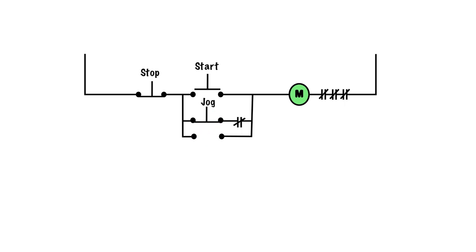And I have actually physically seen it happen many, many, many times in our labs where I teach, just to prove that this circuit. I would say about 50% of the students that wire it up, it works fine when they hit the jog, it just jogs a button. But the other 50%, if they do it quick enough or they kind of hit that button really quickly, it bounces back and the motor keeps running.